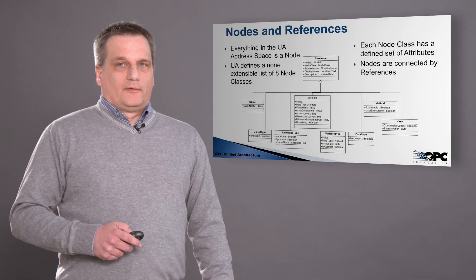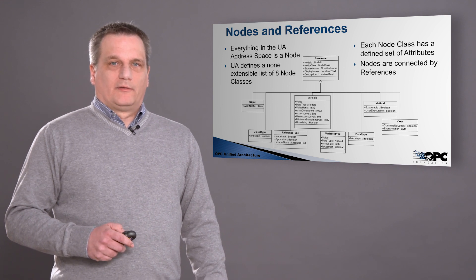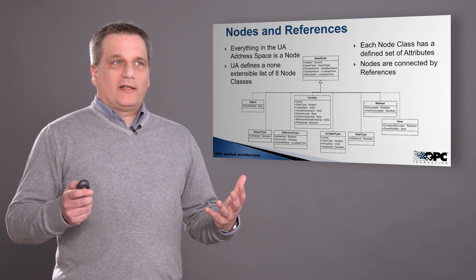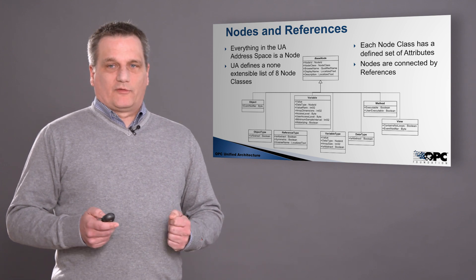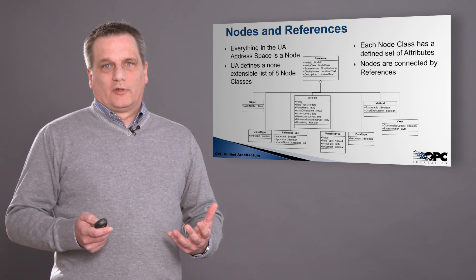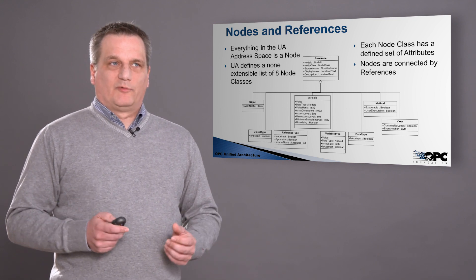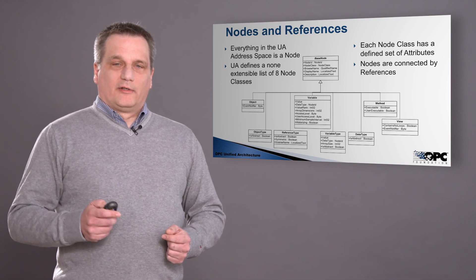We have programs so we can invoke programs or methods, and we have a device description so we can describe the data and the device. The nodes and references in OPC UA are described in eight node classes. The classes can be extended, but the base classes defined by OPC UA are derived from the base node. We have objects and object types, variables, nodes and references, and those have attributes and properties with which we can describe the information. Each node class has attributes and nodes are interconnected with references, which describe the relation between nodes.